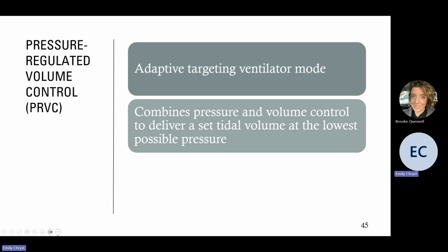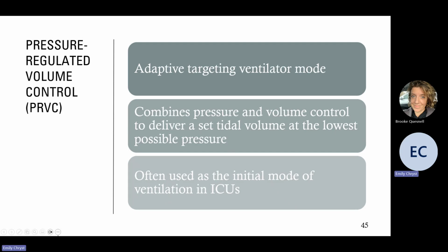So it's going to meet a tidal volume target, but it's going to give the breath in such a way that the lowest possible pressure is delivered to a patient. Higher pressures are going to cause more damage to the lungs, and it's really important that we avoid them. A lot of patients need higher pressures while they're being ventilated. So this mode theoretically allows us to meet our tidal volume targets without having to set an arbitrary pressure to achieve those. It's often, for that reason, used as the initial mode of ventilation in ICUs.